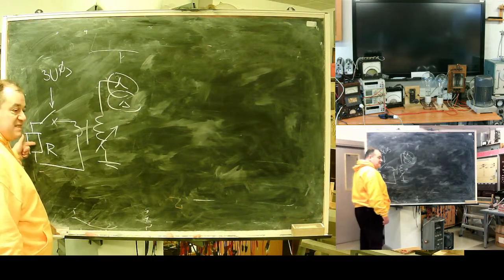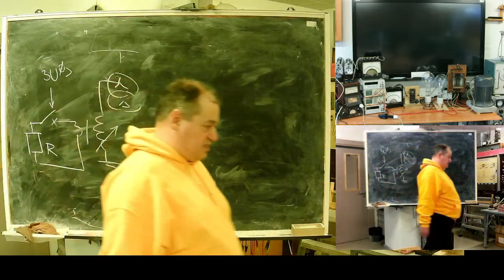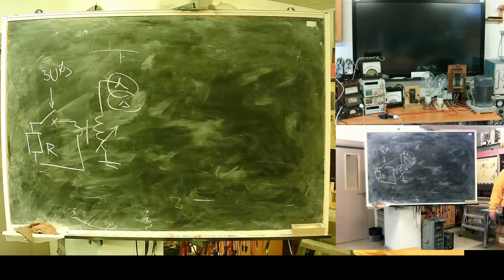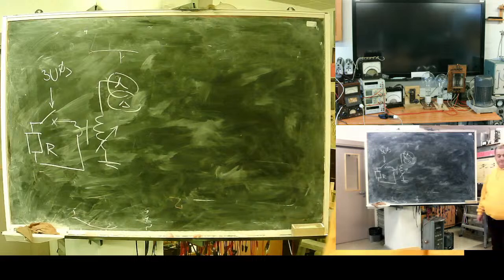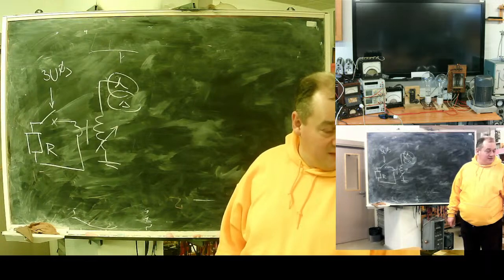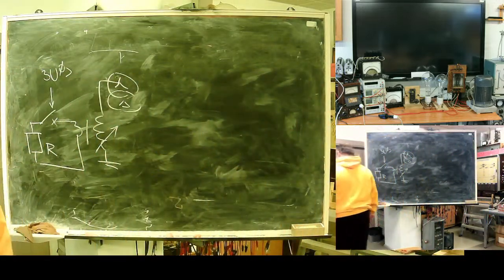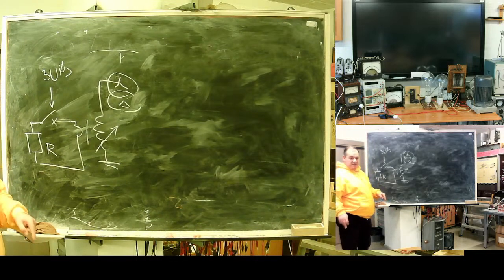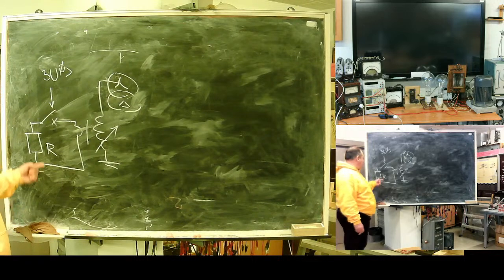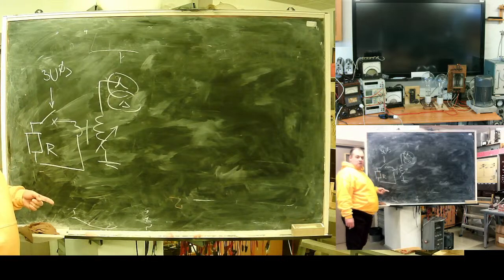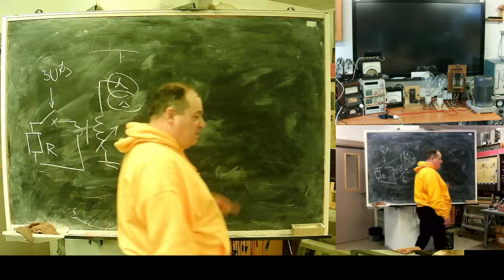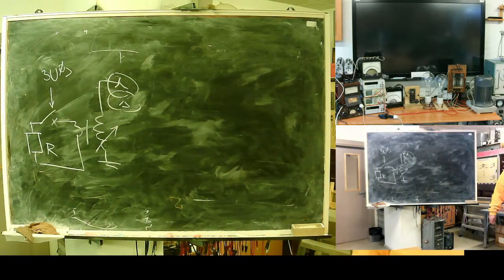Above the withstand or thermal capacity of this resistor. And things are solved when this resistance gets damaged and no one bothers. If resistance is burned, what will we get? Answer: a simple compensated neutral network, where earth fault protection does not operate. Be careful. If it's your responsibility, make sure that this resistor is periodically checked. Otherwise, it can be damaged, protection will not work, someone gets killed, and you will be guilty. It all will fall on your head.